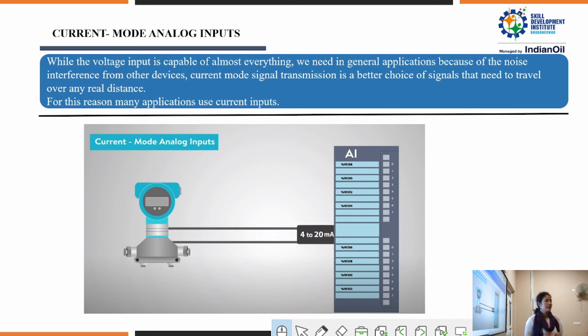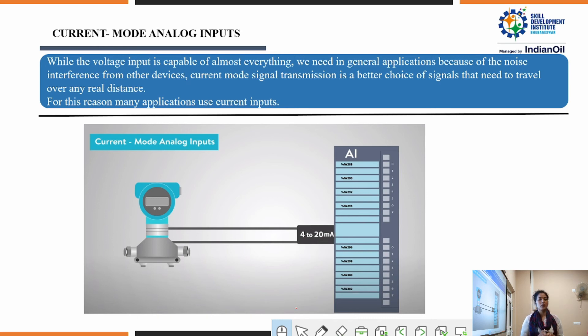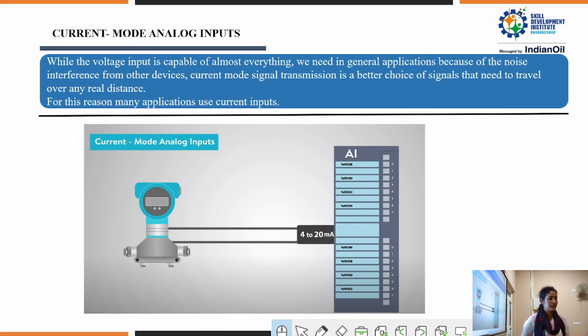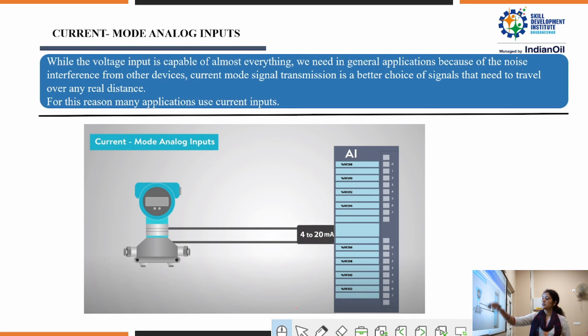In current mode, the industry is nowadays using current mode analog inputs because in current mode there is no noise or humidity interference occurring inside the signal. While voltage input is capable of almost everything, before — because of noise interference from other devices — current mode signal transmission is a better choice for signals that need to travel over any real distance. For this reason, we are now taking applications in the form of current inputs. This smart transmitter gives a current signal of 4 to 20 milliamps which is fed to a controller.